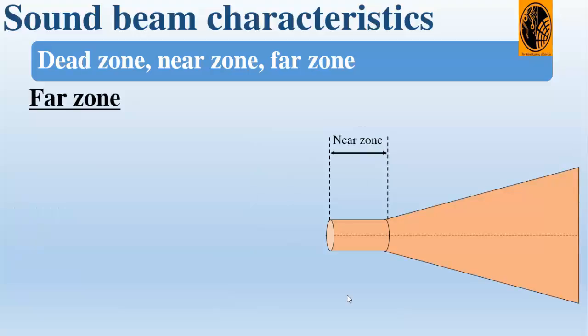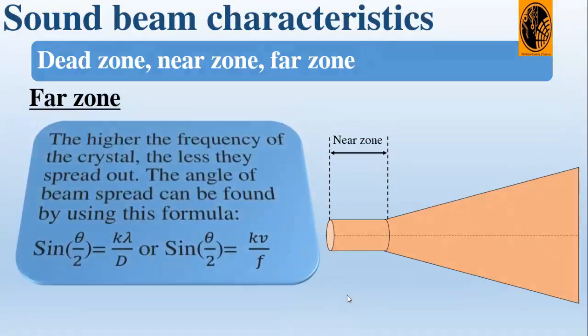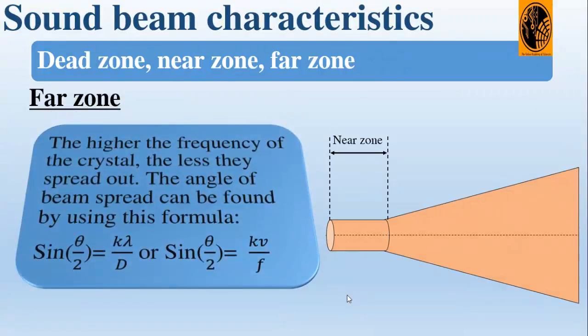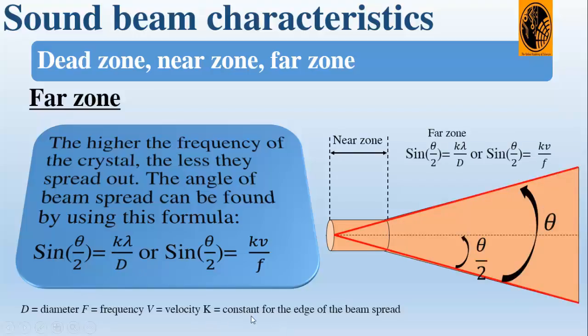Another characteristic of the sound beam is the far zone. The far zone can be worked out using the formula sin(θ/2) = Kλ/D, where D is the crystal diameter. K is a constant for the edge of the beam spread.